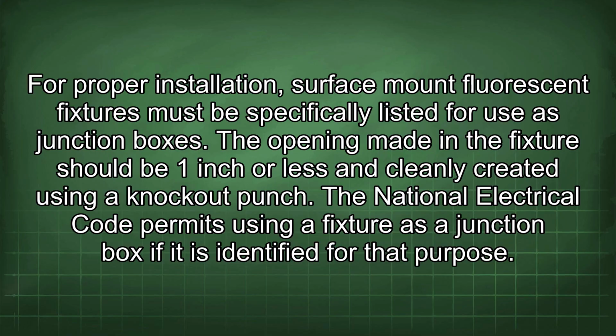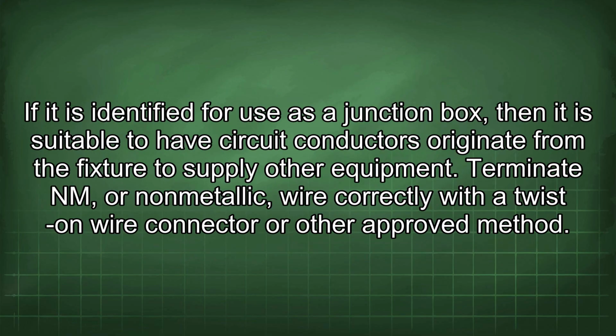The opening made in the fixture should be 1 inch or less and cleanly created using a knockout punch. The National Electrical Code permits using a fixture as a junction box if it is identified for that purpose. If it is identified for use as a junction box, then it is suitable to have circuit conductors originate from the fixture to supply other equipment.